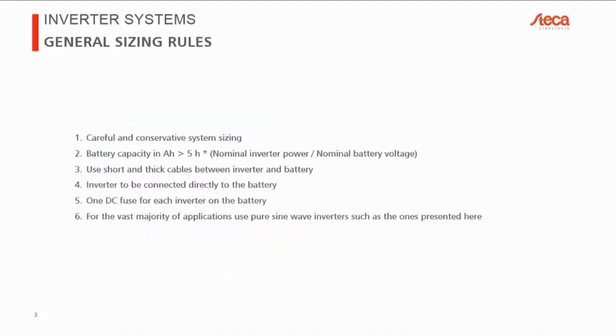So here are 5 general rules you should keep in mind when you're designing systems with inverters inside. The first point is careful and conservative system sizing. We don't have the time today to go into detailed sizing of a PV off-grid system, but suffice to say that if you develop a PV off-grid system, and if you miscalculate only by a little bit the consumption, or rather the production compared to the consumption, then things can go wrong quite dramatically.